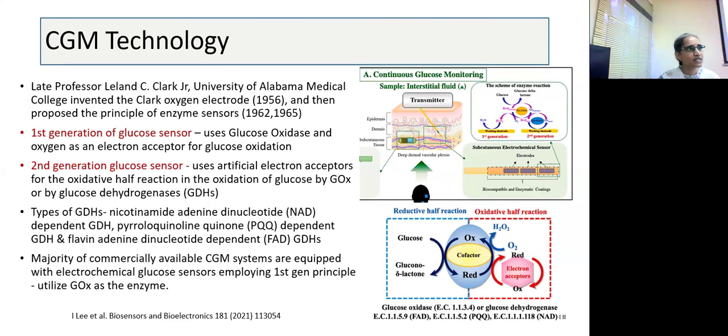We have the glucose oxidase systems and the glucose dehydrogenase systems and glucose dehydrogenase pyrroloquinoline quinone, that is GDH-PQQ systems as well. So it is the same type of sensor for the glucometers as well as the CGM devices.